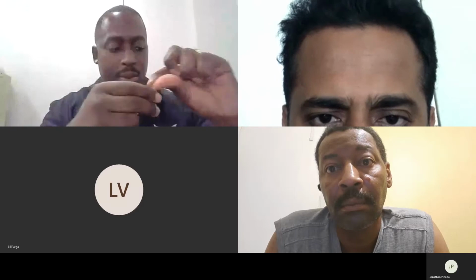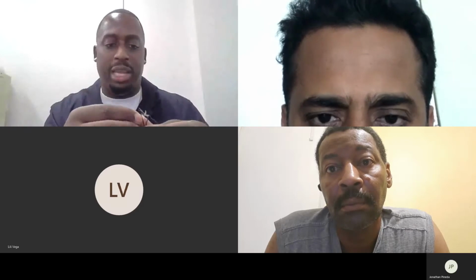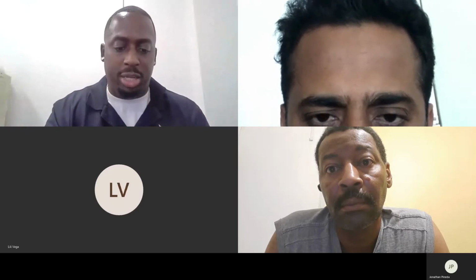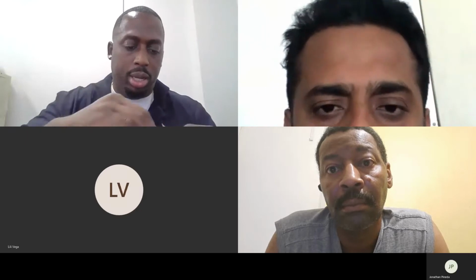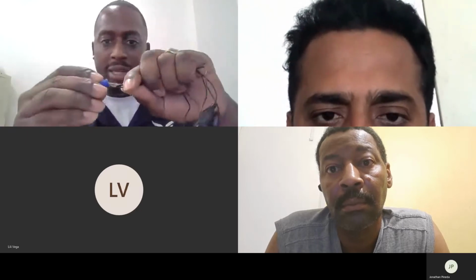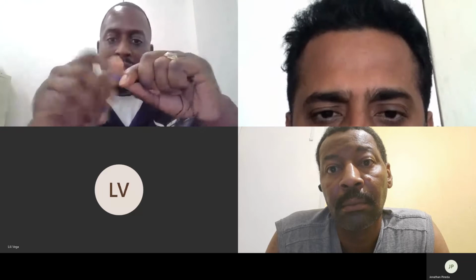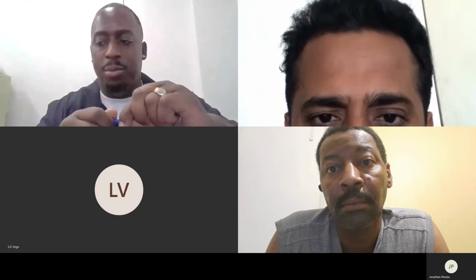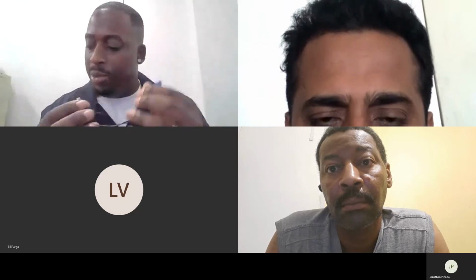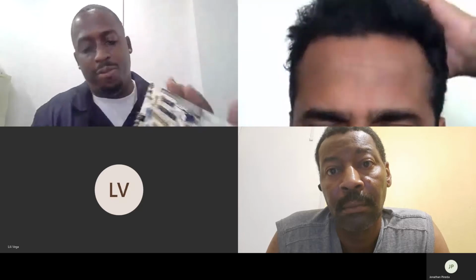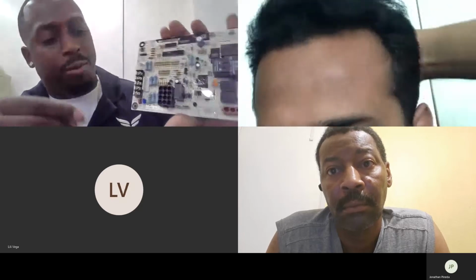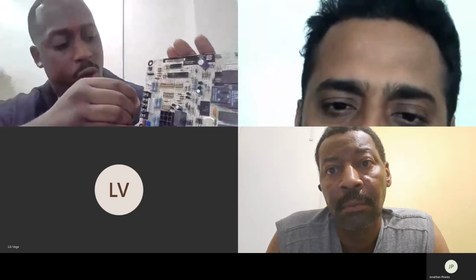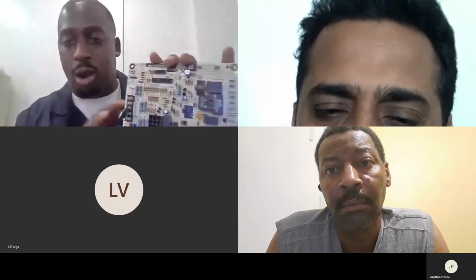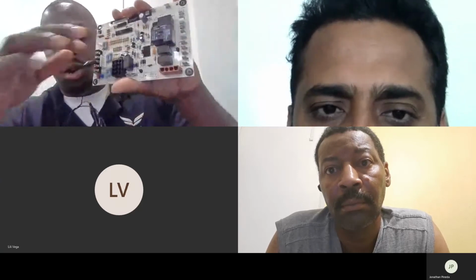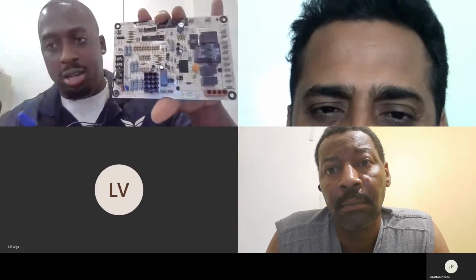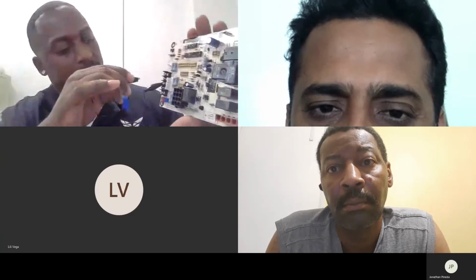But what I usually do is cut them, and I like to put at least 4 of them together. So I cut them and strip them, and I wire nut them all together like this. That way I can connect more than one thing more easily. So what I would do is, if I wanted to test the fan, I would connect one of these to R, because R is the 24-volt supply. R is constantly hot. So I'll connect one to R, and then I'll connect another alligator clip to G.